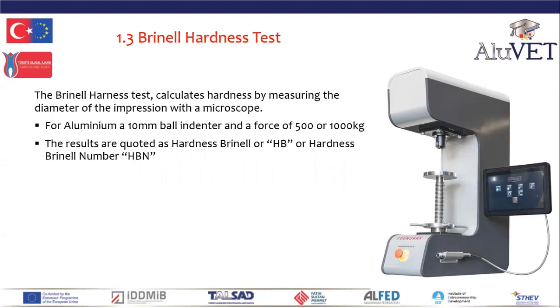The larger impression and the greater load means that the test is more tolerant of surface imperfections and more of an average value. It's more of a macro test. We have to prepare the surface for Brinell hardness testing. So again, it has to be parallel and ground flat. And we need to grind it to approximately a 200 grit.